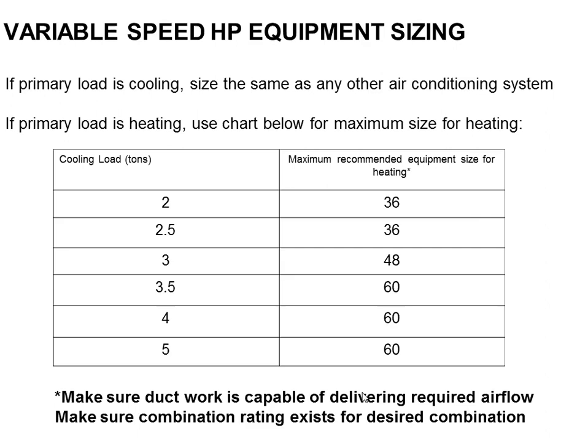This is the sizing chart right out of the book for these Extreme and Greenspeed heat pumps. And basically they're trying to get you to round up. So if you had a 2 ton cooling load, they're saying put in the 3 ton heat pump, 36,000 BTU heat pump. If you had a 3-ton, they're saying put a 4-ton in. If you had a 3.5, they're saying put a 5-ton in. And if you had a 4 or 5-ton cooling load, they're also saying put a 5-ton in. So you're not really upsizing on the 5-ton only because the biggest size they have available is a 5-ton. So you can't really get any bigger than that. But it'd be nice if you could, obviously, if they had a 6-ton.